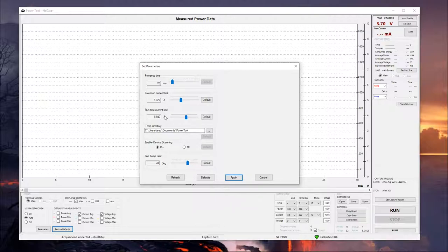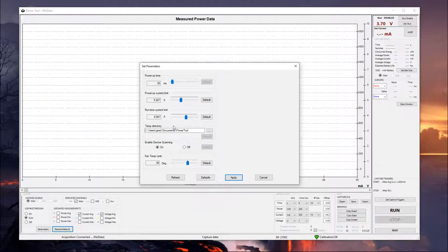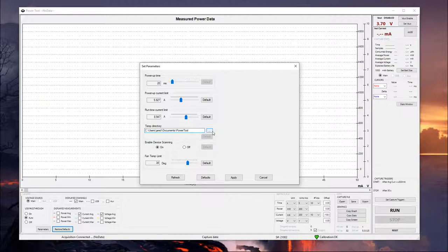Same with the runtime current limit. If it sees an amperage higher than this value as you're taking a test, it's going to trip that protection circuit and disable the voltage so as to protect your device. The temporary directory, this is just where the measurement is going to be stored on a temporary basis. It records everything from the device to a temporary file before it saves it permanently, and this will be the location of that file.